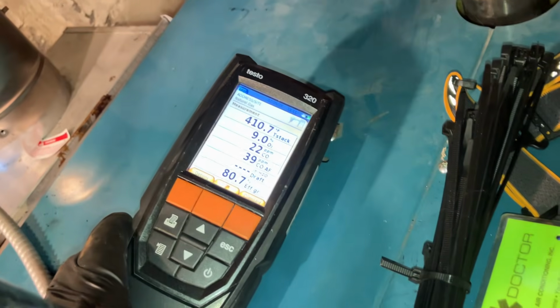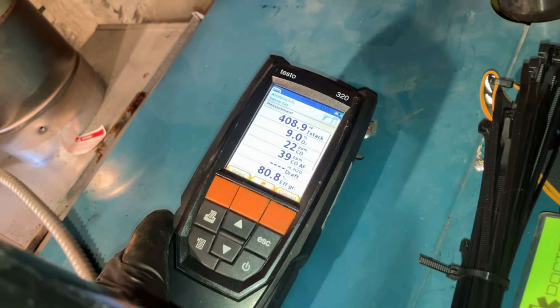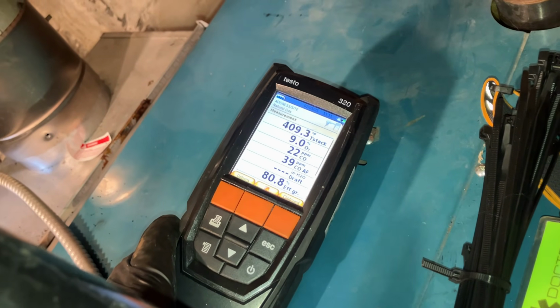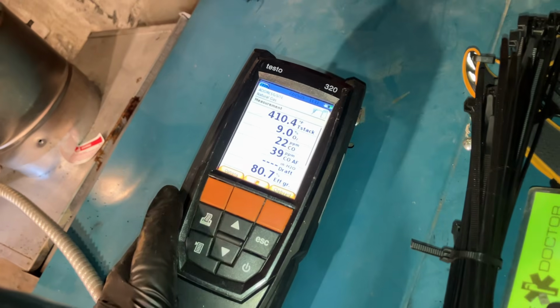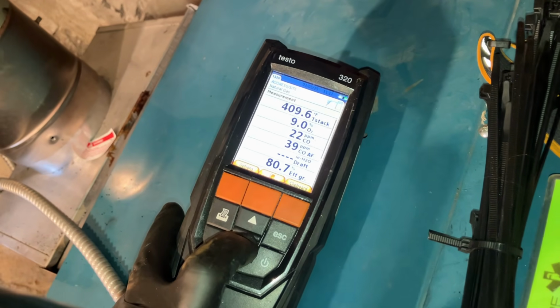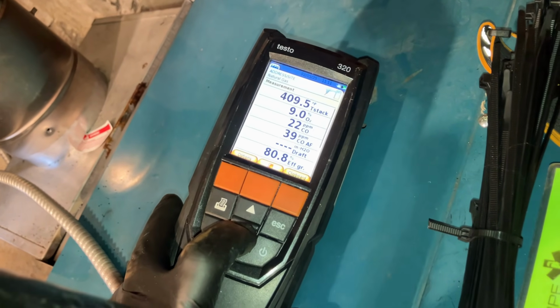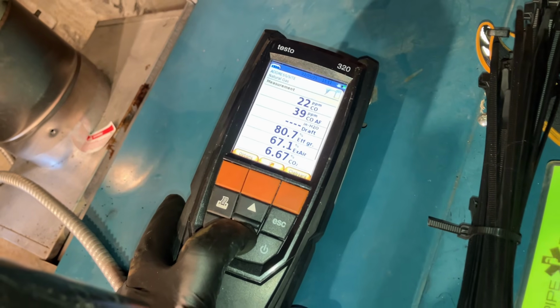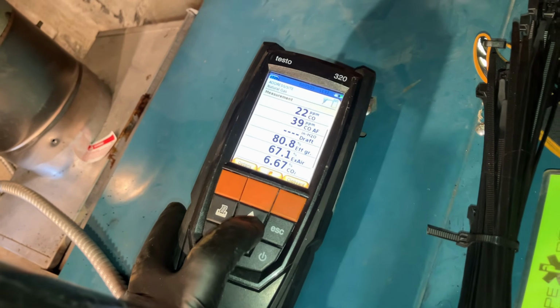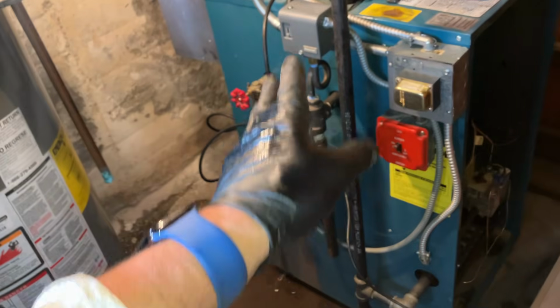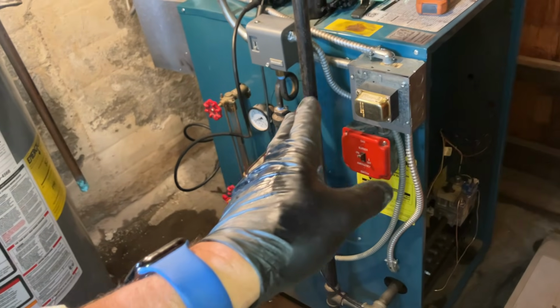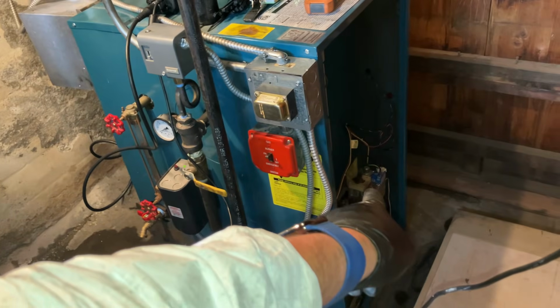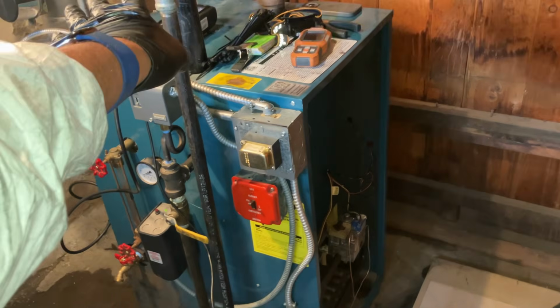All right, we are at a stack temperature of 410 degrees, an O2 reading of 9, 22 parts per million of carbon monoxide, a gross efficiency of 80.9, and CO2 of 6.67. All those numbers are perfect. So now that I know that's okay, I'm not going to check the gas pressure on the gas valve. My numbers are fine. No need to check that.